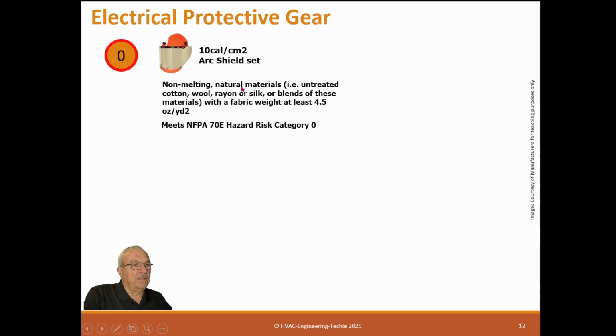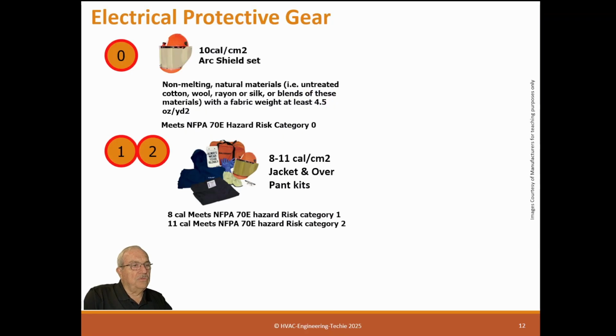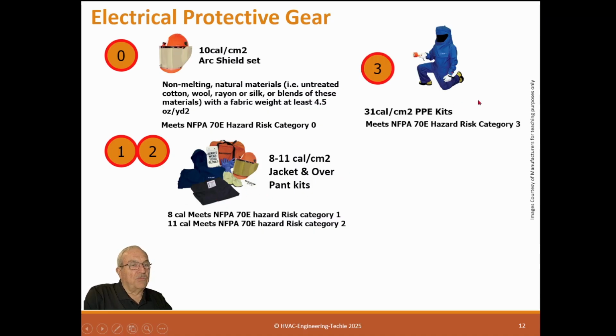So here's the protective gear. This is that 0, and it's just face protection, basically. It's regular cotton clothes for construction, low flammability materials, standard things. Eye protection is what's required for this. Class 1 and 2 is 8 to 11 calories, and you can see that it has gloves, it has face shields, it has hoods. And the 3 is a full suit. This one doesn't have pants, but this one has a full suit. It's much larger. It has darkened faceplates. It's much more difficult to get around in a 3 than in a 1.